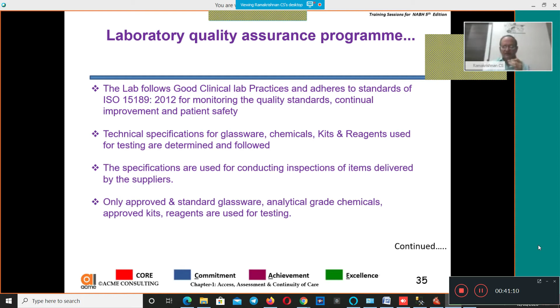Standard glassware, etc. will be used. Again, chemical materials will be analytical grade, where we talk about appropriate purity levels, right? And storage of the chemicals is very important. There are some reagents that require room temperature, some require 8 degrees. Appropriately, the temperature and the storage will be maintained. That's why you require a fridge. The kits we use need to be maintained at particular temperature, including appropriate humidity conditions, as specified by the manufacturer. So these need to be stored effectively so as not to lose the efficacy of those chemicals that will be used.